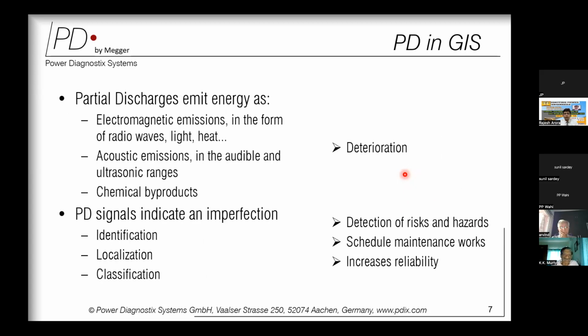Now, whenever partial discharge occurs in GIS, there are good and bad things associated with it. If we talk about the good things, electromagnetic emission takes place because of this dissipation of energy, in the form of radio waves, light or heat, and sometimes also acoustic emission. The good part is that whenever these emissions take place, they are measurable. We can use some detection methods and quantify this emission, and hence measure the quantum of partial discharge. The bad part associated with partial discharge is the deterioration phenomenon: once PD occurs, the insulation starts deteriorating and it is going to accelerate over a period of time, giving birth to a phenomenon called the aging mechanism.